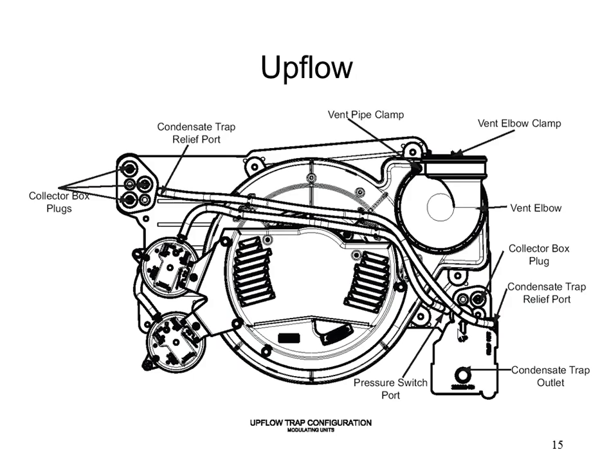This kind of shows you a little bit of the inside of this guy. So up here in the top right is actually the exhaust elbow, the vent elbow coming out of the heat exchanger. This guy rotates, and I'll show you some pictures of that in a little bit here. But he rotates to go up, left, right, or down if we were to flip the furnace over. This right now is showing an upflow configuration, so air is coming in the bottom of the drawing, moving its way through the top and out the top. So this is the way it comes shipped as a default. Everything's fantastic. The vent elbow is pointed up.